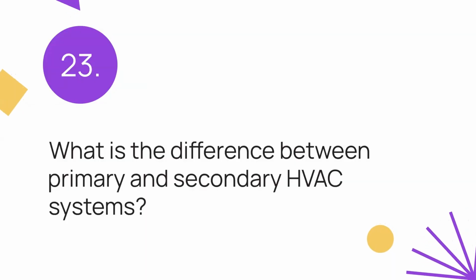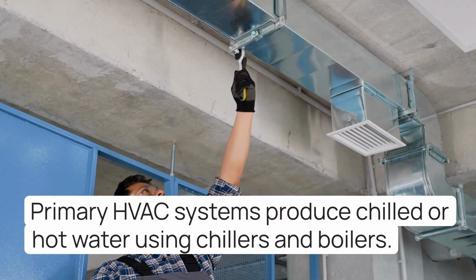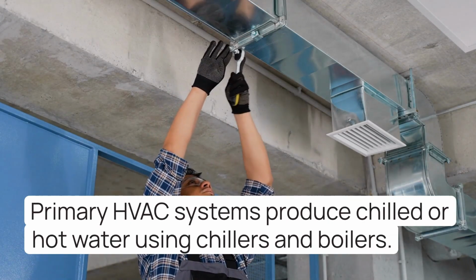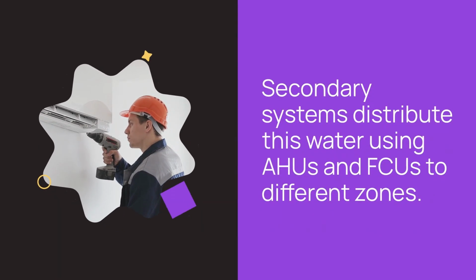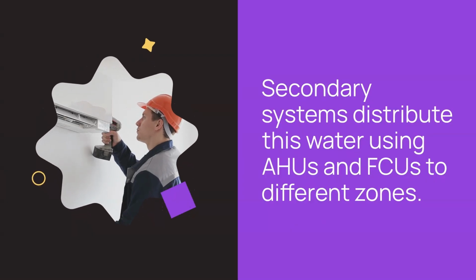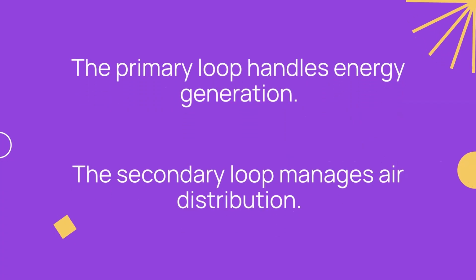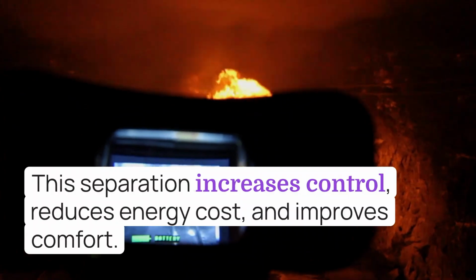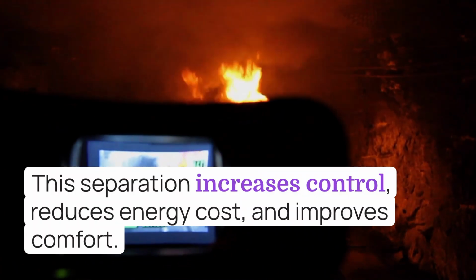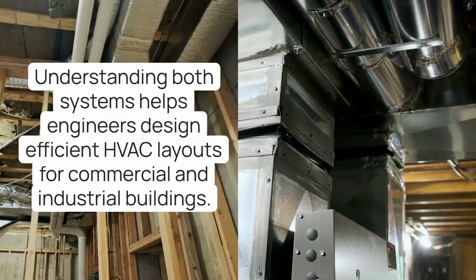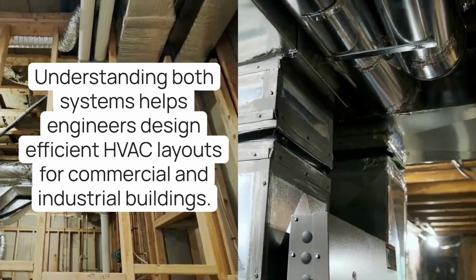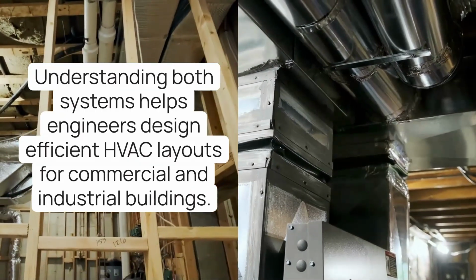23. What is the difference between primary and secondary HVAC systems? Primary HVAC systems produce chilled or hot water using chillers and boilers. Secondary systems distribute this water using AHUs and FCUs to different zones. The primary loop handles energy generation, while the secondary loop manages air distribution. This separation increases control, reduces energy cost, and improves comfort. Understanding both systems helps engineers design efficient HVAC layouts for commercial and industrial buildings.